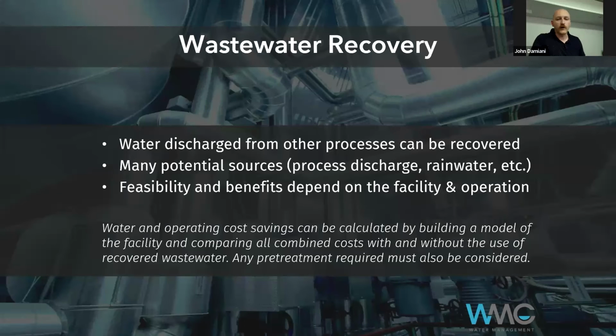Wastewater recovery is another option. Any water discharged from other processes can be recovered, and there are a lot of potential sources suitable for cooling towers. That's a nice thing compared to steam systems. Process discharge and rainwater can be options. The feasibility and benefits depend on how much waste water is available and what treatment you need. You often can't just send it straight to the tower; there's usually some pretreatment step required, which adds cost, so you have to look at it from an engineering standpoint to see if it's worth it.